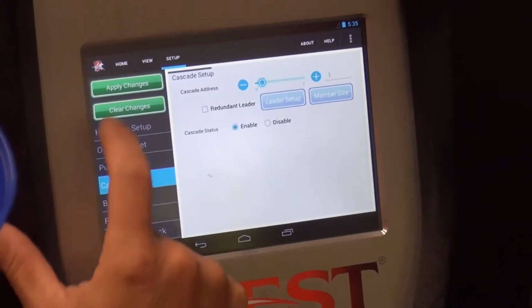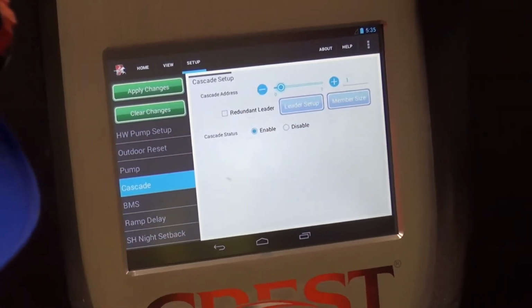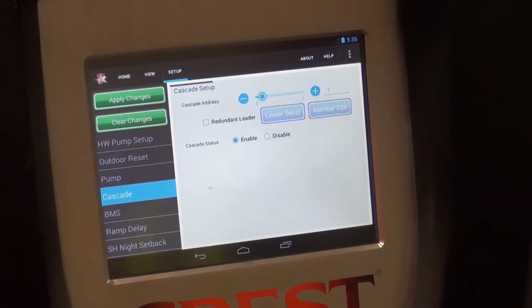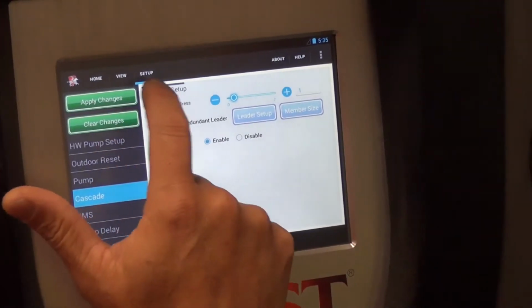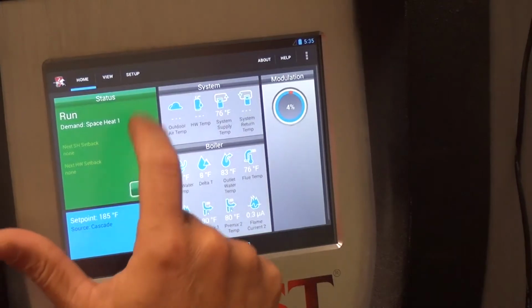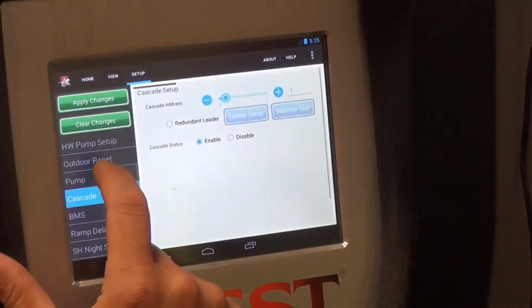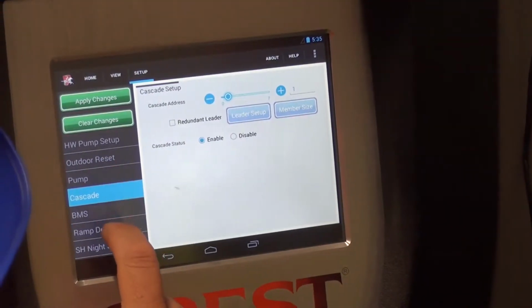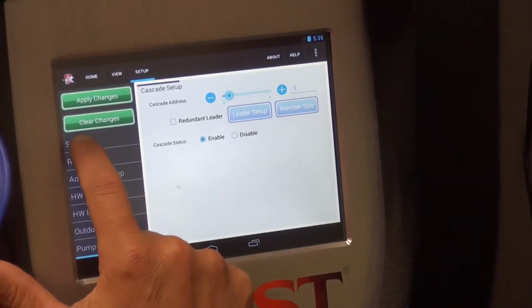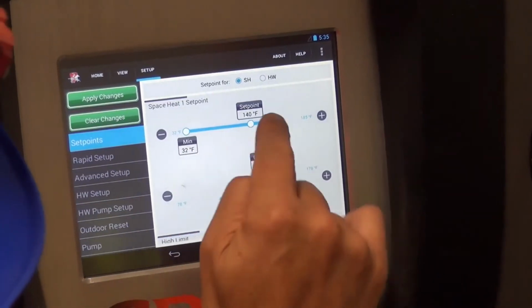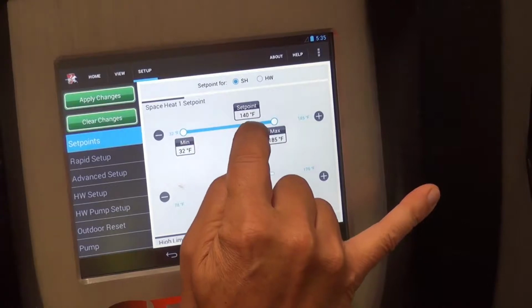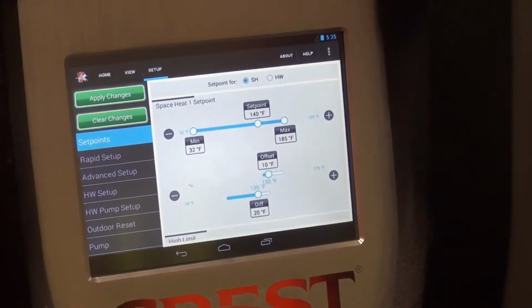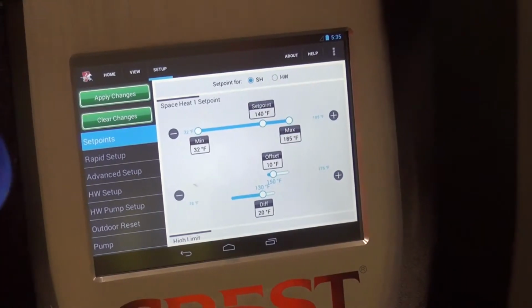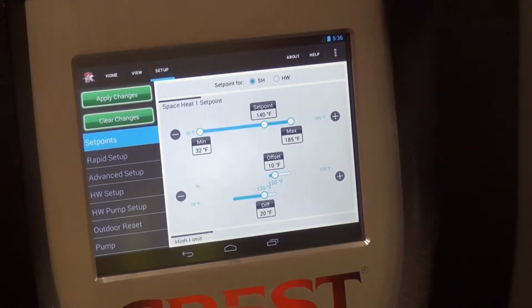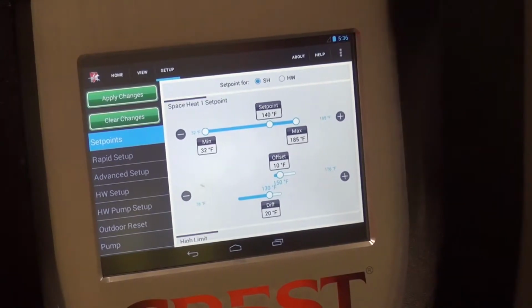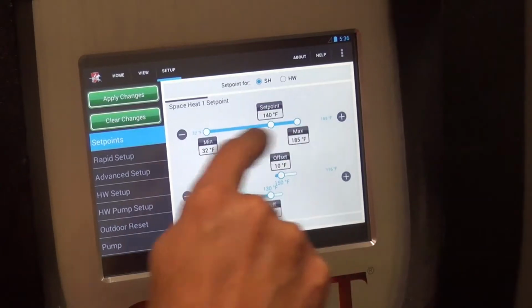And then you should be able to do everything. This one will start operating on its own, because we already have it set so it'll work off of these temperatures. Its set point will be now 150. That's what it'll target, since we don't have full control over it, it's only measuring the outlet temperature sensor, so it's going to bounce off of that temperature.